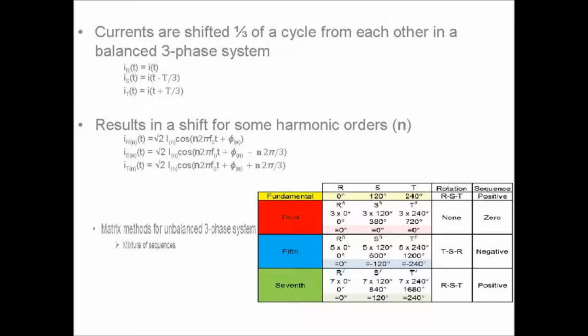Obviously, fifth is particularly bad to have because it means you've got to do extra work to overcome on your generator or your motor. Whereas the seventh is more like the fundamental, it's spinning in the positive direction, so it's actually helping a little bit. It's still got currents there, so it's going to heat up your generator or your motor or whatever it happens to be. This is all for a balanced system, I suppose. If it's unbalanced, you have to use matrix methods.